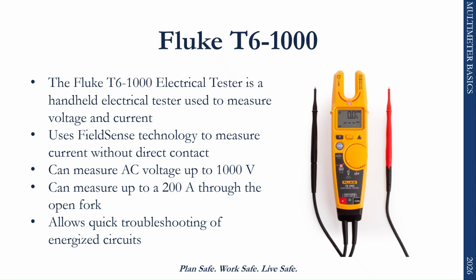The Fluke T6-1000 electrical tester is another piece of equipment that may be used in the field for electrical measurement and troubleshooting. One of the main advantages of this tester is its open fork design, which allows it to measure current without disconnecting conductors. It can measure AC voltage up to 1000 volts and current up to 200 amps. This tester also uses field sense technology, which allows current measurements to be taken without direct contact with the conductor. This can make troubleshooting faster and reduce the need for additional connections when diagnosing energized circuits.